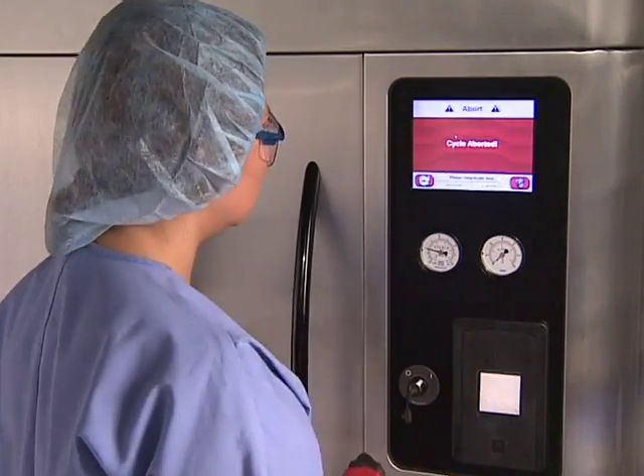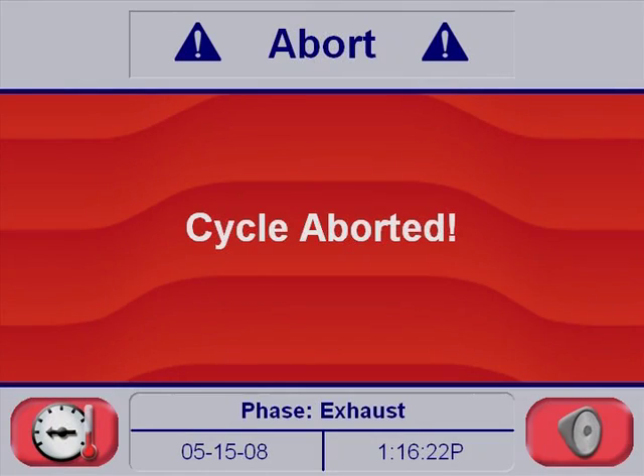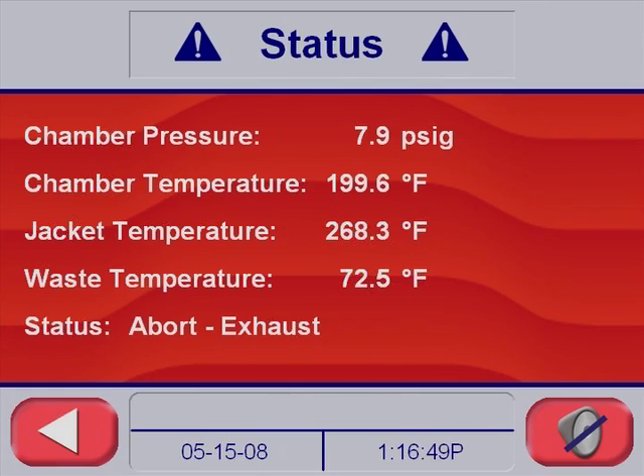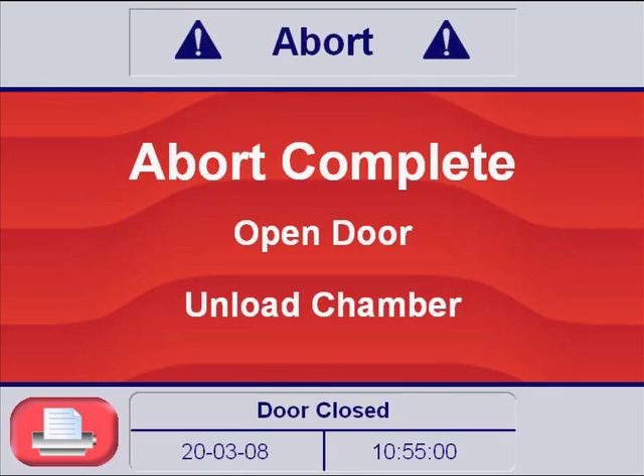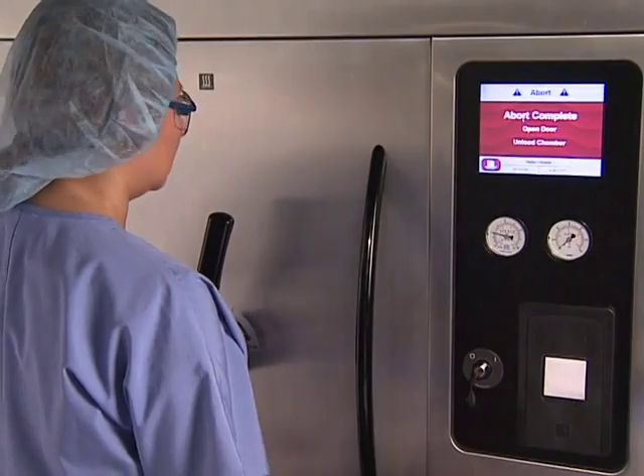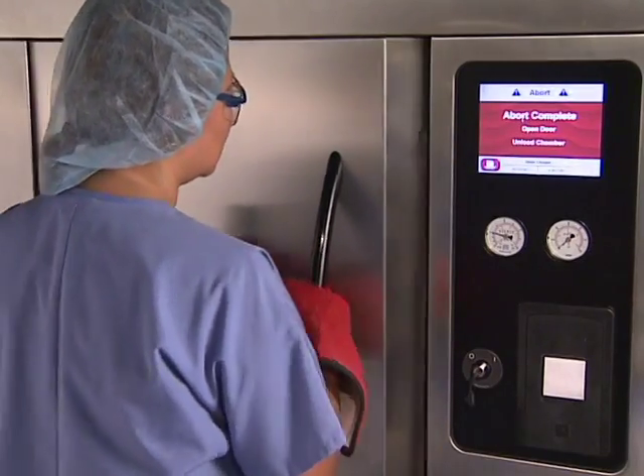You'll hear a Cycle Abort tone, and the sterilizer will exhaust the chamber of the steam, returning it to atmospheric pressure. Press the Silence Alarm button to turn off the alarm. Press the Status touchpad to show an abort status screen. Once the vapor has been removed, the control panel displays an Abort Complete message. Open the door and safely unload the chamber.